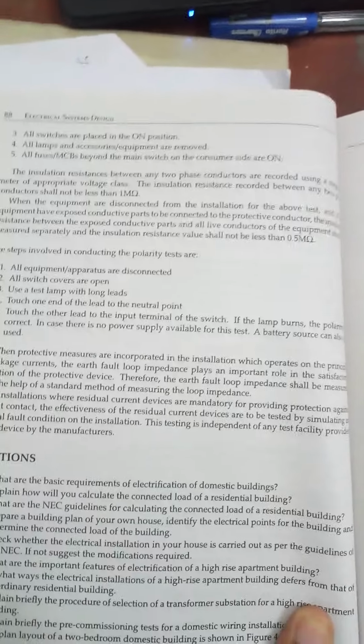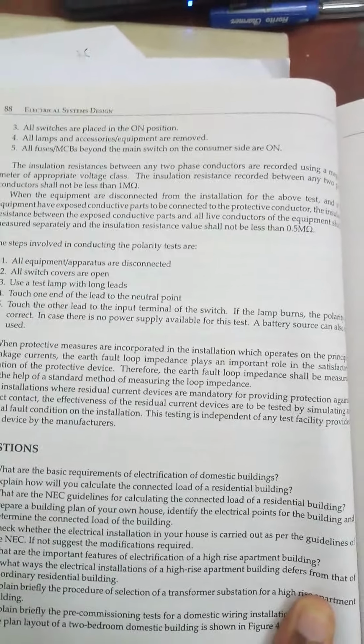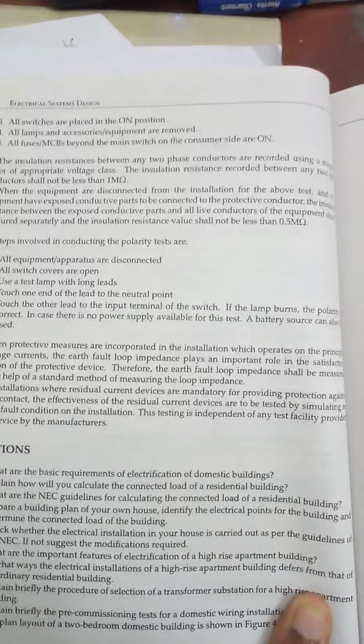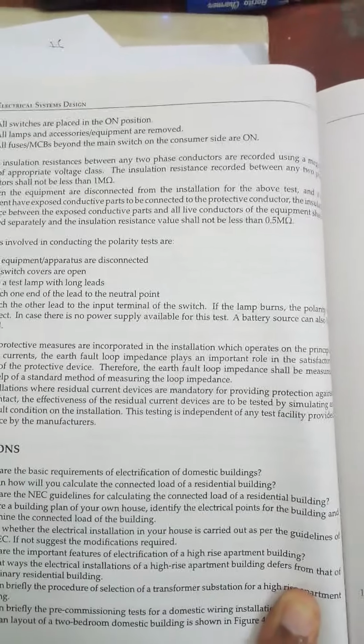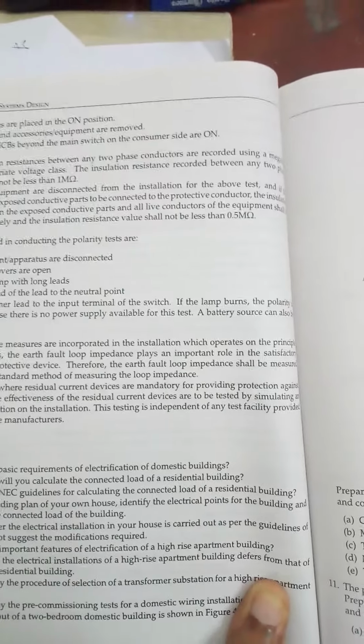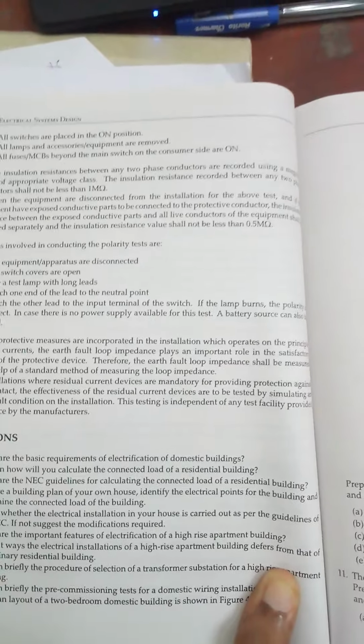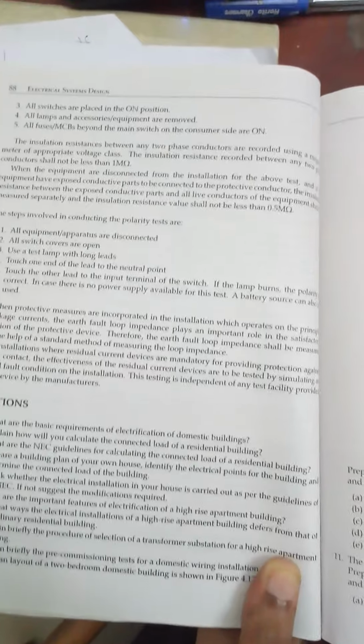The steps followed in conducting the polarity test are: all equipment is disconnected, all switches are kept open, use a test lamp with a long lead, touch one end of the lead to the neutral point, touch the other end to the input terminal of the switch. If the lamp burns, the polarity is correct. A battery source can also be used for this purpose.